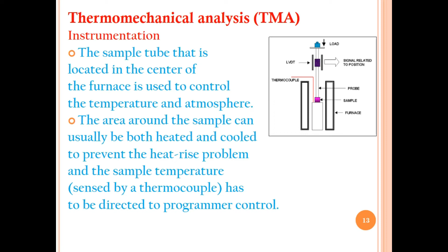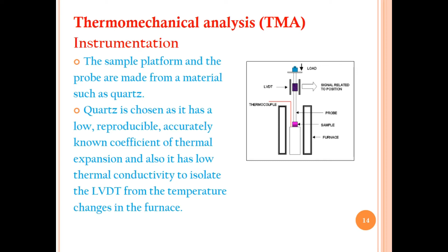Instrumentation is continued. The sample platform and the probe are made from a material such as quartz. Quartz is an inert material, and the material must not react with the sample under observation. Quartz is chosen as it has a low, reproducible, accurately known coefficient of thermal expansion. It also has low thermal conductivity to isolate the LVDT from the temperature change in the furnace.